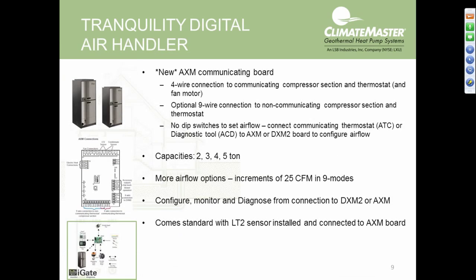Our air handler to be matched up with that is the TAH Rev B with the new AXM control board that communicates with the DXM2. But you also have the option of non-communication. So if you had one of the new air handlers with an older TTS, you can still make that connection and have the unit work properly. Capacities in the air handler to match our splits are 2, 3, 4, and 5-ton. The airflow is adjusted through, and we're going to get more into this in the technical portion of this presentation, the service tool or the thermostat. And we can adjust in 25 CFM increments.